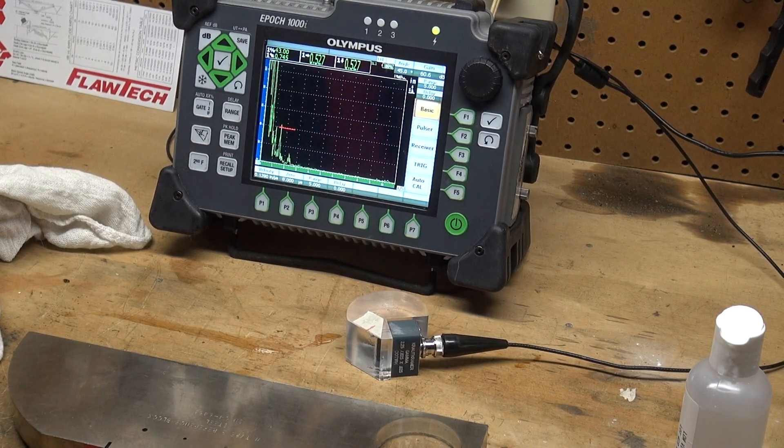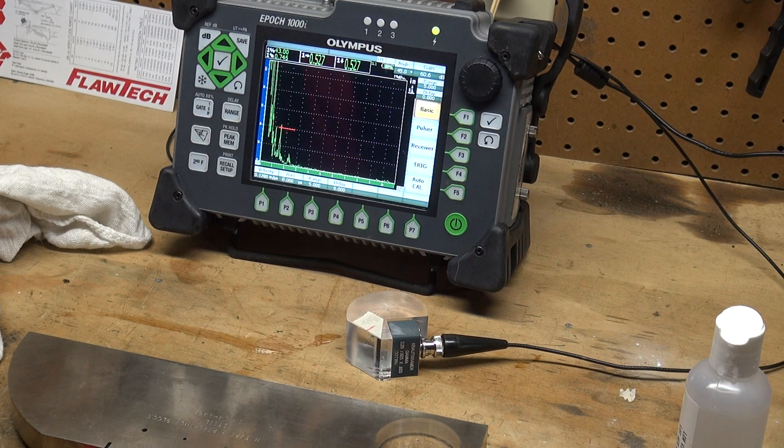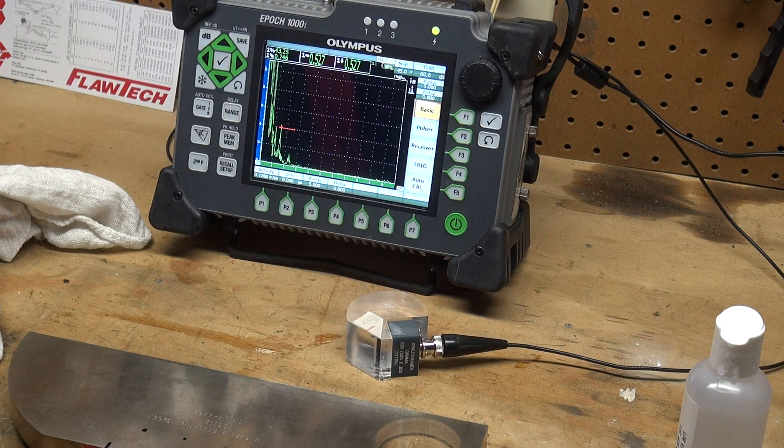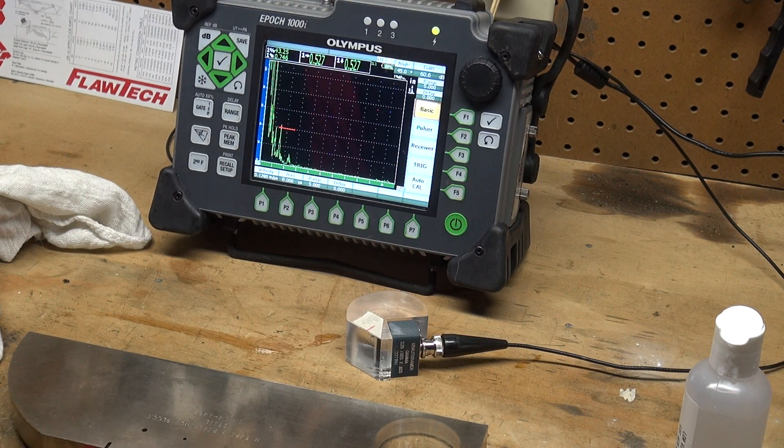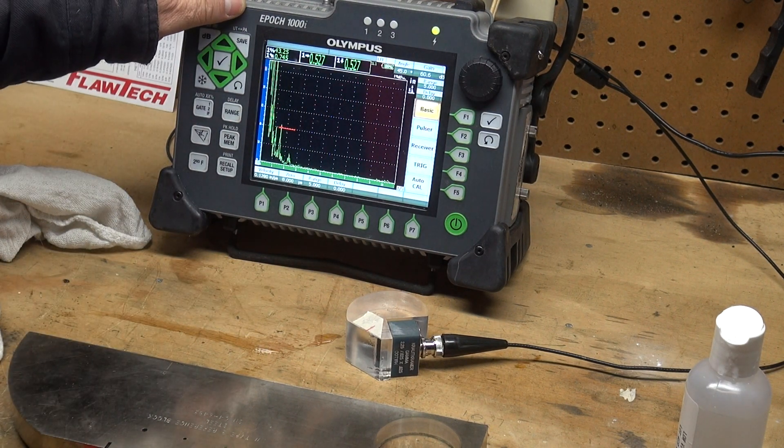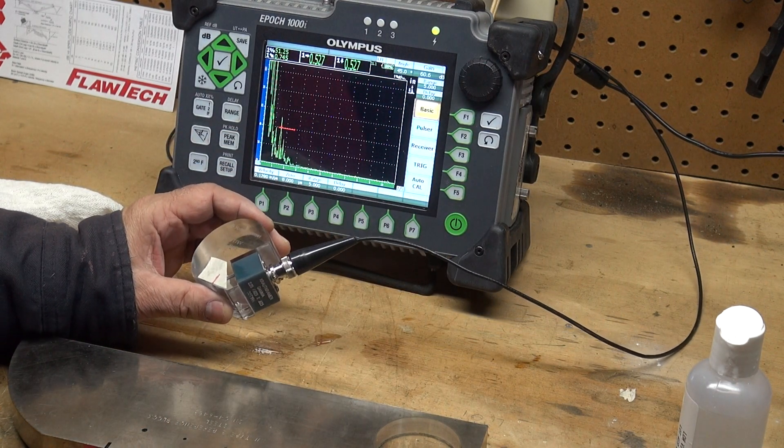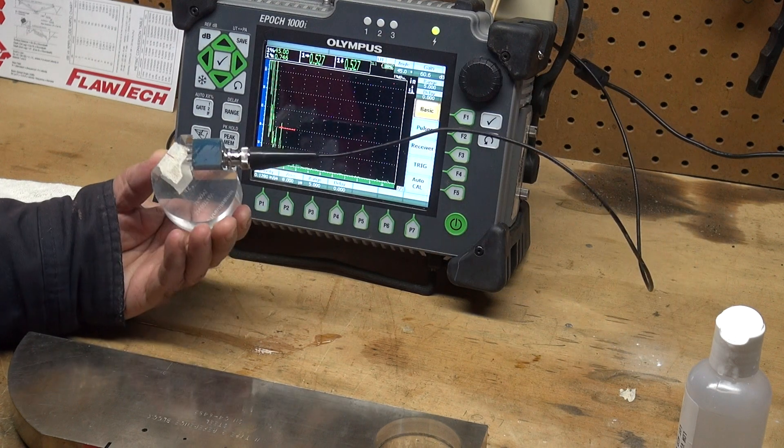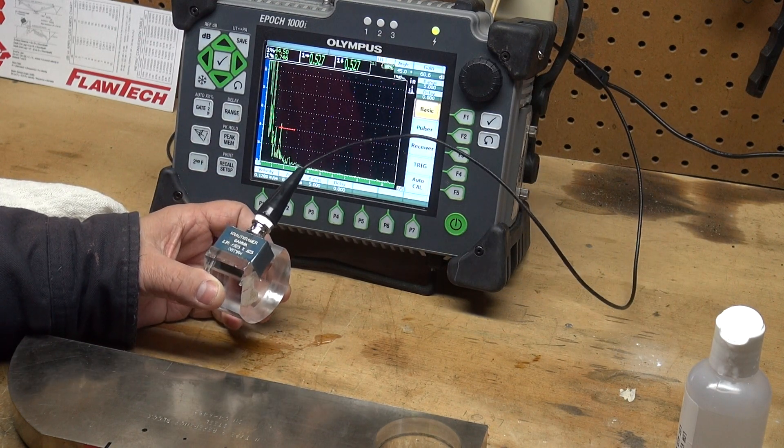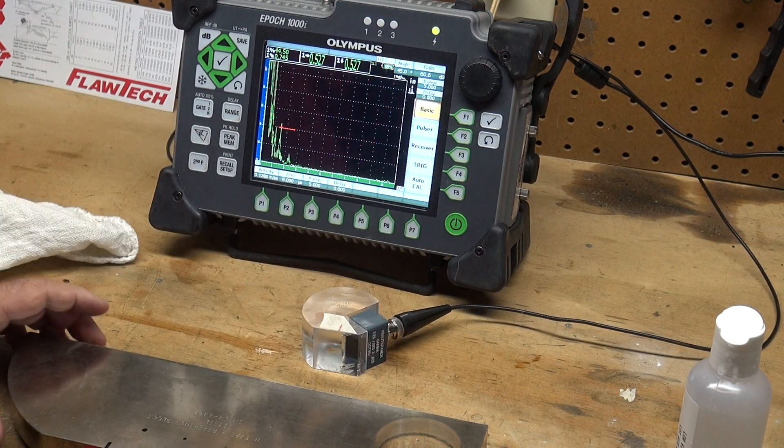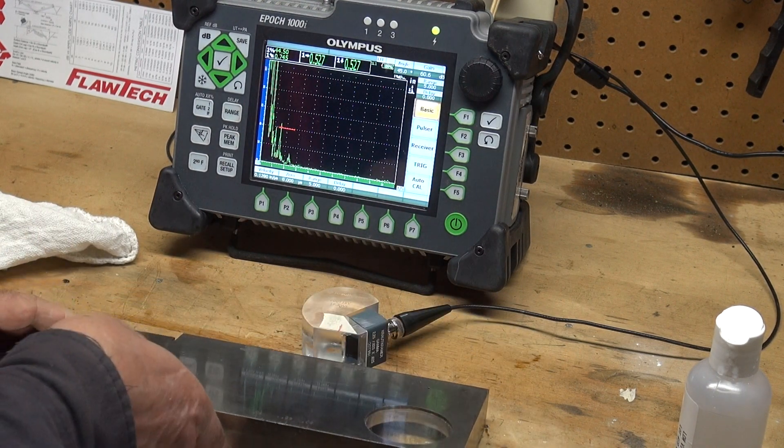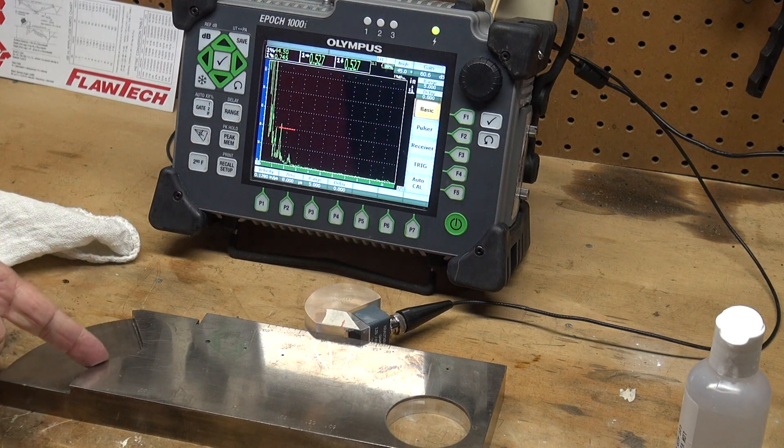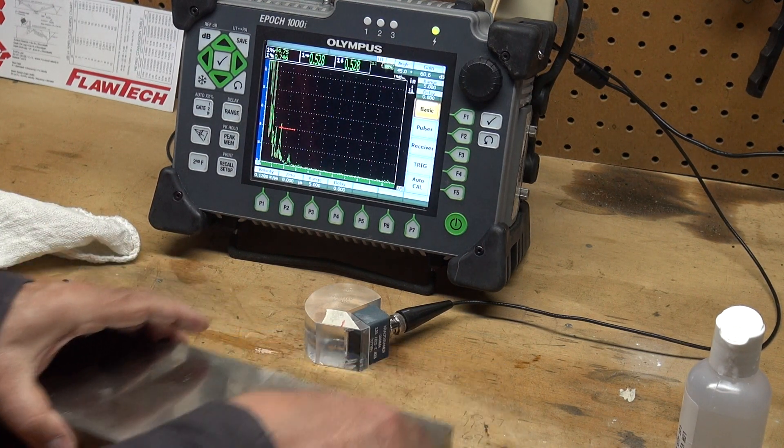I'm going to go over calibration of angle beam contact ultrasonic testing using an IIW type 2 block. The equipment I have is the EPOCH 1000i from Olympus and I'm using an AWS wedge which is 45 degrees. I'm using a 2.25 megahertz transducer. The type 2 IIW block has a 2 and 4 inch radius, so those are the two reflectors that we will use for calibration.